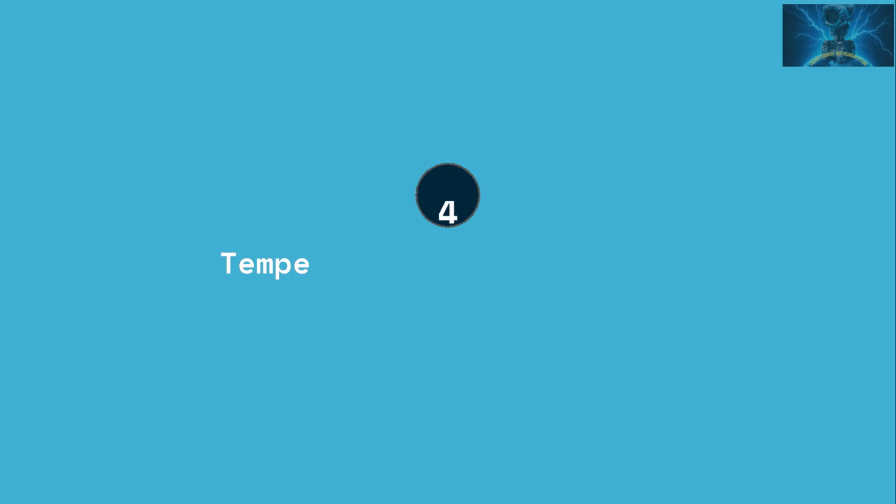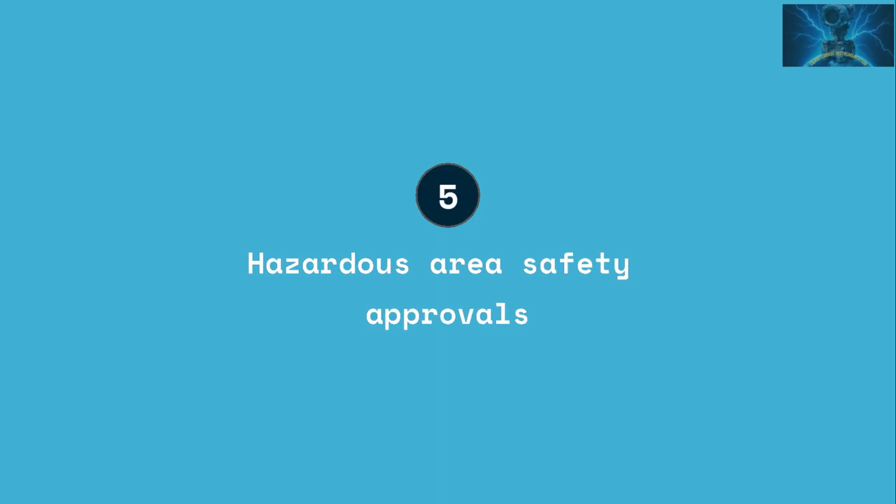Temperature and pressure: verify probe and gasket ratings. Watch thermal expansion that can detune small gap sensors. Hazardous areas: use intrinsically safe transmitters and approved barriers where flammable atmospheres exist.